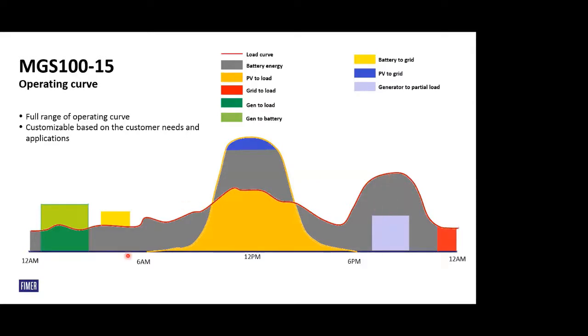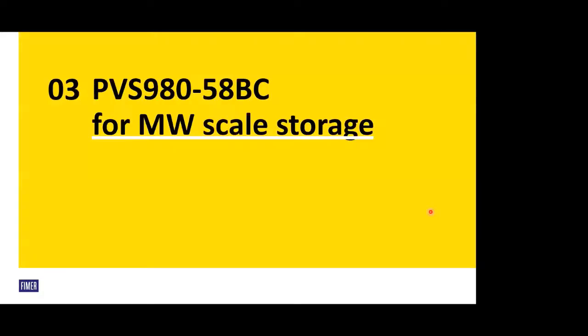And if you still want to use it like a typical on-grid system, if the grid is a good source, whenever the grid comes you can deliver to load and also charge the batteries. So it is all very simple to control, and not necessarily do you need all the sources at one particular load, but these are the capabilities of any microgrid system per se. You can choose what time and what source to use for what functionality: whether your grid delivers only to load, or to load as well as batteries, or you want generation to deliver only to load, or load and batteries. These are the things you can control in a typical microgrid.